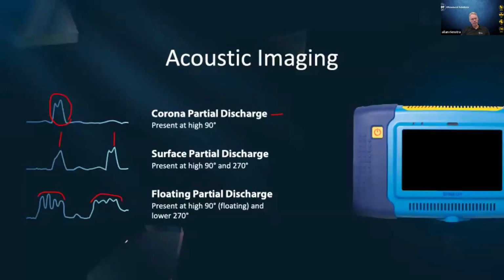These acoustic imaging cameras, they're quite good. Distance-wise, the one that we make is capable of detecting sources of partial discharge that are as far away as 200 meters, probably further than 200 meters. They work really well at 20 to 50 meters. They're not really designed for close-up inspections, so I wouldn't use it around switchgear panels, but substations, transformers, transmission distribution lines, that's really what they're designed for. Because they're just detecting airborne ultrasound, they're also a wonderful tool to use for finding sources of compressed air leaks at far distances.